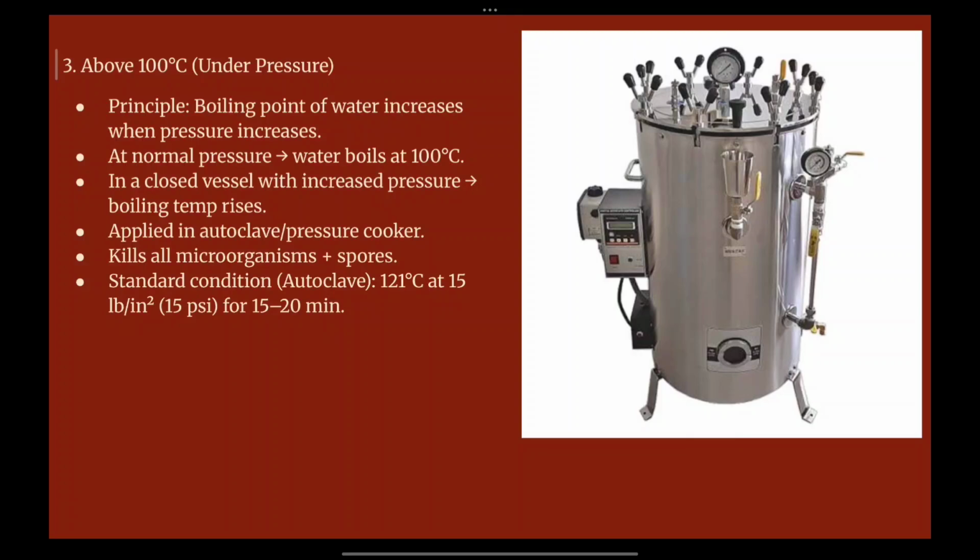So the standard condition for sterilization above 100 degrees Celsius, as in the case of an autoclave, is 121 degrees Celsius at 15 psi pressure for 15 to 20 minutes. So that is how the sterilization is conducted. The water is boiled, and once the water boils, there is increased pressure and conversion of water into steam.